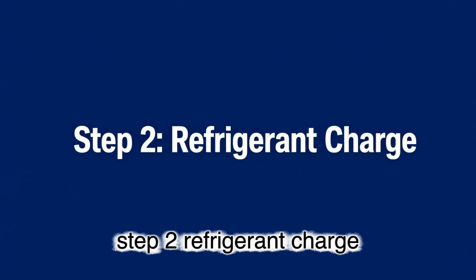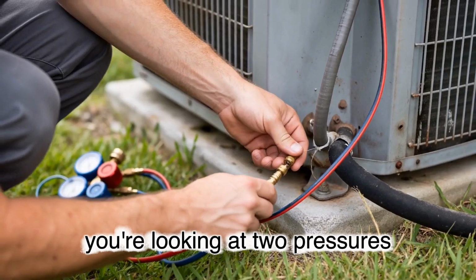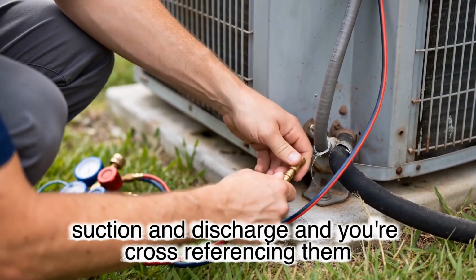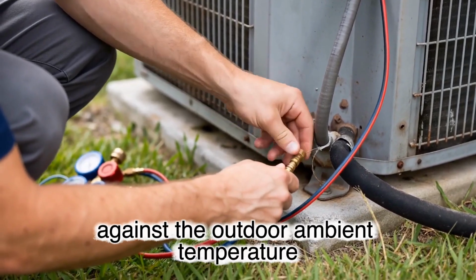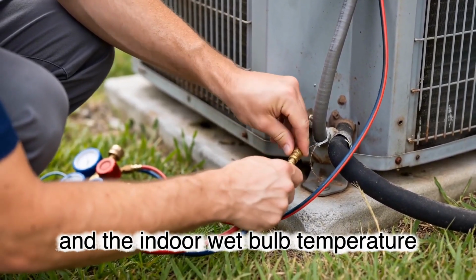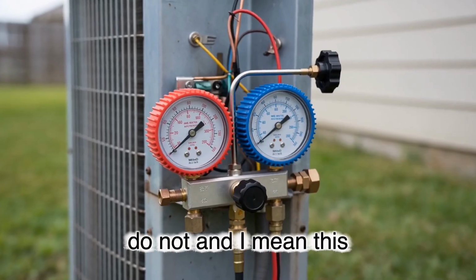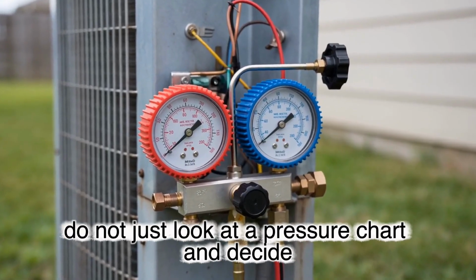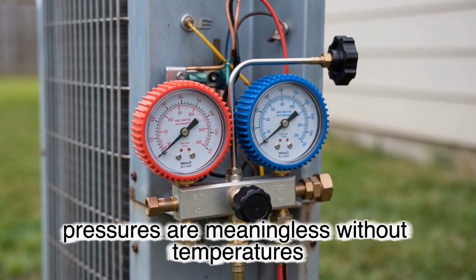Step 2, refrigerant charge. You're looking at two pressures, suction and discharge, and you're cross-referencing them against the outdoor ambient temperature and the indoor wet bulb temperature. Do not, and I mean this, do not just look at a pressure chart and decide the system is low. Pressures are meaningless without temperatures.